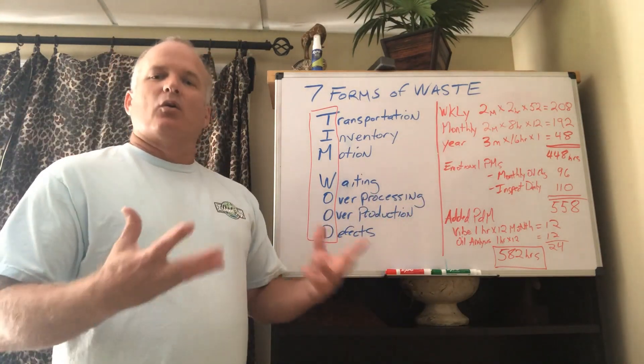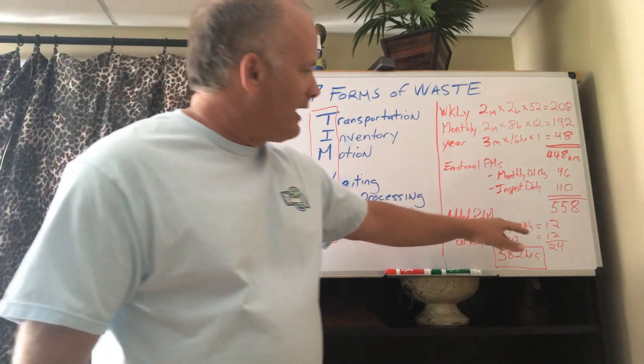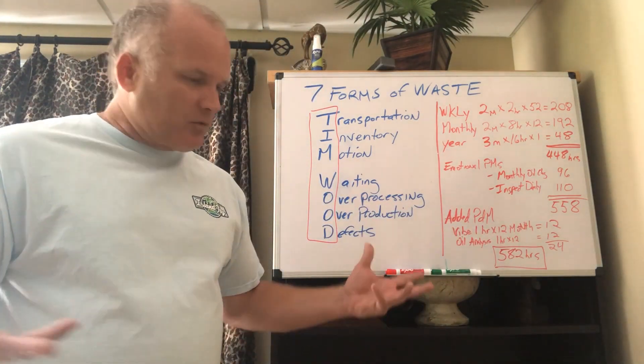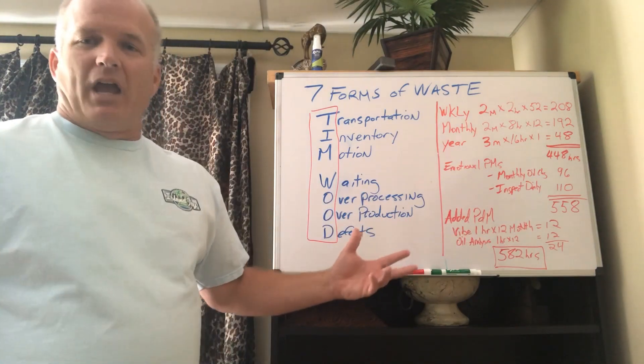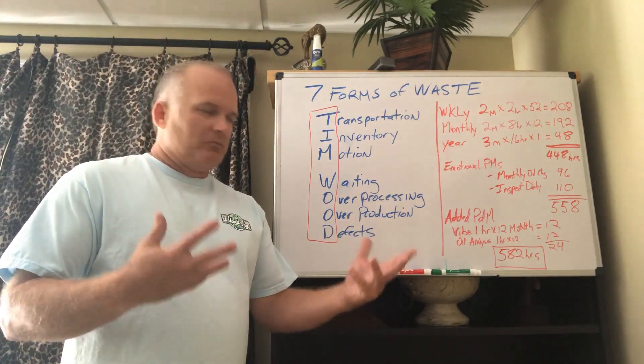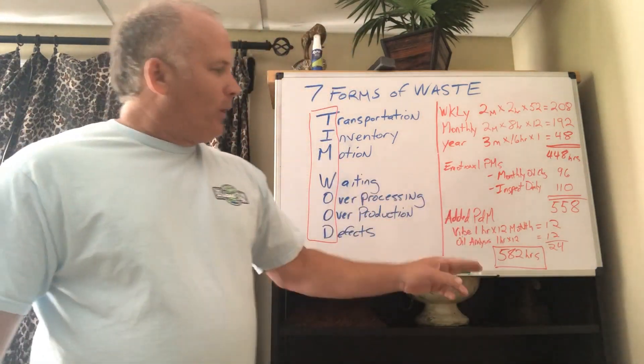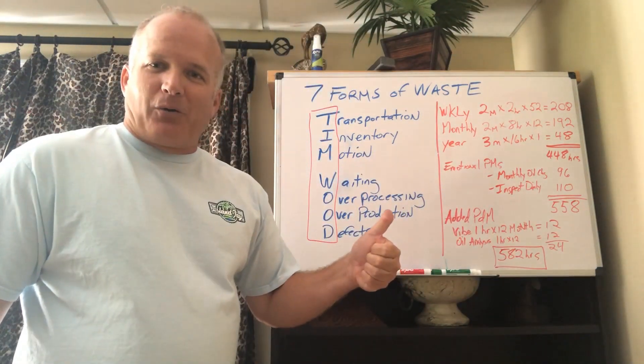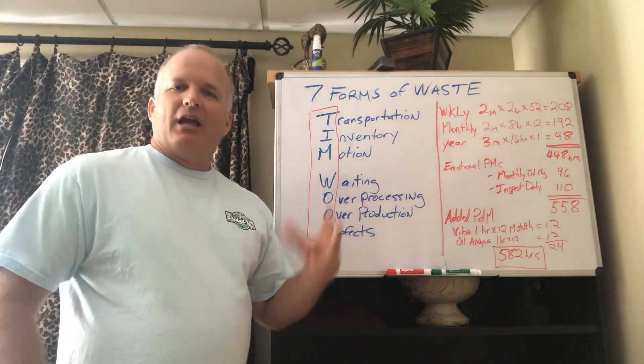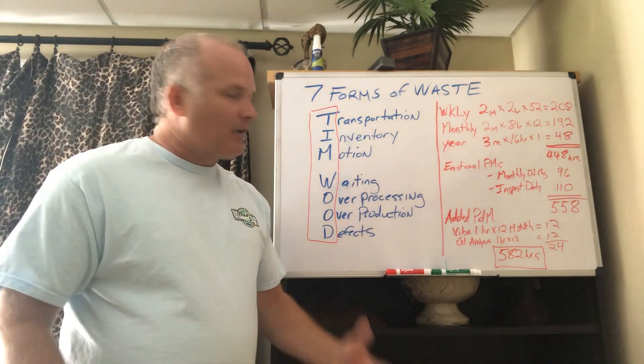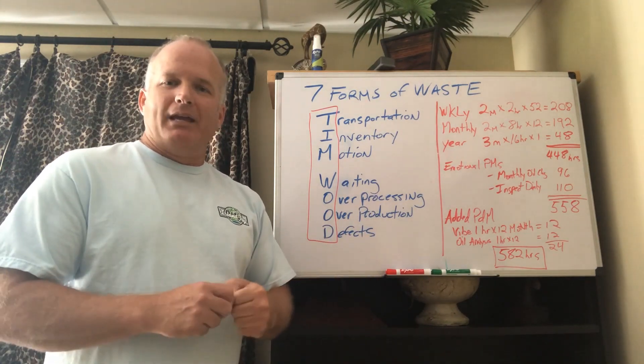So what do we do to get control of this quickly? If you go all in on condition monitoring — that's what you're about, science and data — you can run this asset on 24 hours of PDM. Say you still do an oil change every six months; even then you're up to 40 hours. That's your new PM program. Versus 582 hours — that's a 93% reduction in the hours invested on this one asset. You may generate some corrective work, but a 93% reduction in PM hours on just this one asset.